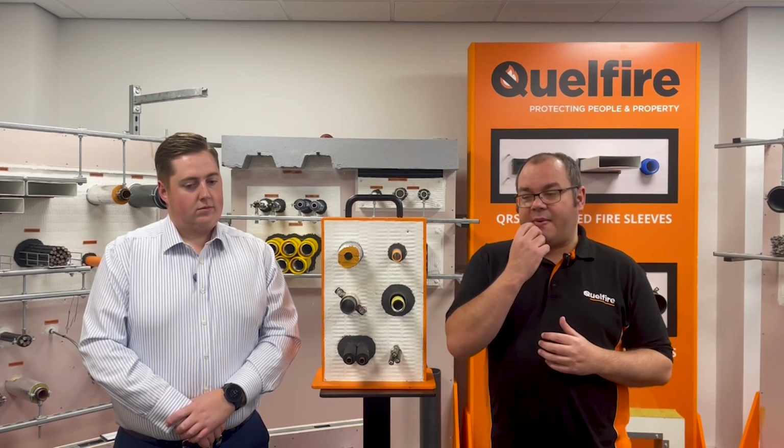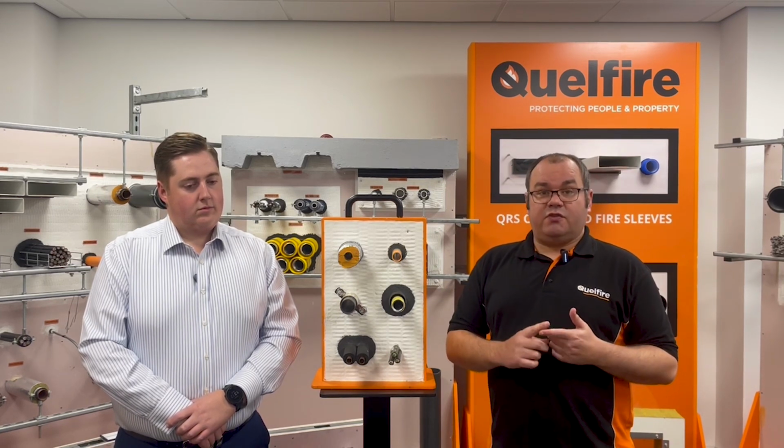We've got underfloor Busbars that can then be used with our raised floor access details with our QuelStop Firebatt. We've got Busbars through flexible walls. We have both now circular ducts, 75mm and 90mm, semi-rigid circular ducts through Firebatt, which we didn't have before. If you go to our insulated metal pipe details, for example, we now have more flexibility with 90 kg density rock fiber instead of 120. So this allows you to use insulation from Paroc and Knauf, not just rock wool.